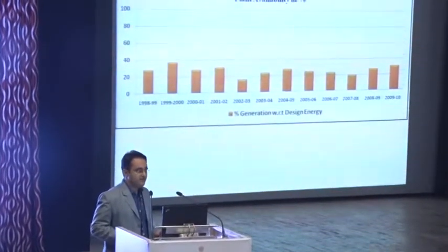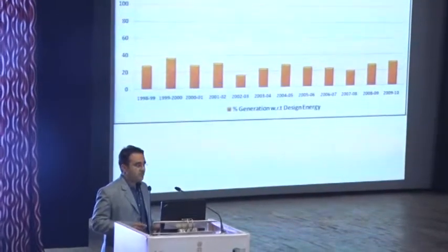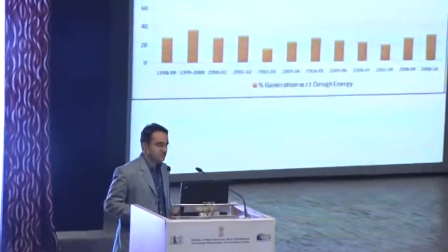In this, we have taken this Chiplima dam, which is of 22 megawatt. The biggest problem with this project is the lower generation, and the reason is the trash. The project is suffering with the problem of perennial weeds. These weeds are so thick and come and choke the trash rack panel. I still remember in the year 2009-10, the first time I visited the site, I was standing on the intake and I saw a soccer field in front of me.